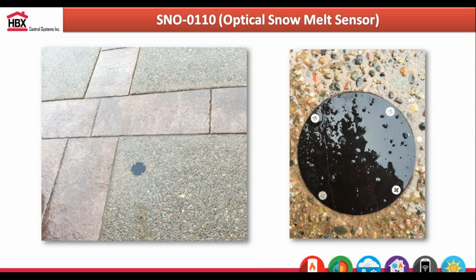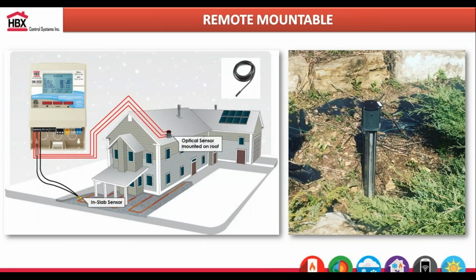With our sensor, it actually has a snowfall indicator as well. So in that rare scenario where you were backing out of your driveway and had some snow on your truck and it fell on that sensor, it won't trigger. It'll melt that snow, but the sensor knows that some snow just got on it, it's not actually snowing, so we won't trigger a melt mode. Whereas if you were using a TECMAR sensor, it would just assume that it's snowing and would trigger 8-hour snow melt mode, depending on how many hours you put into that controller. So that's where you get the advantage of using the optics in your snow melt sensor. We also have the capability of using that sensor remotely.